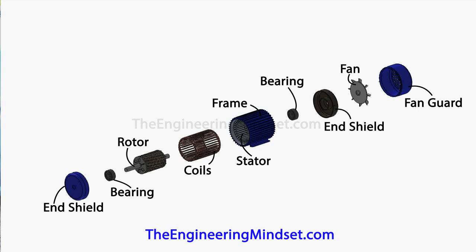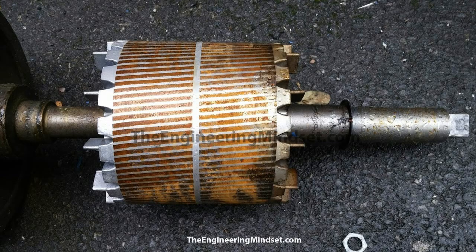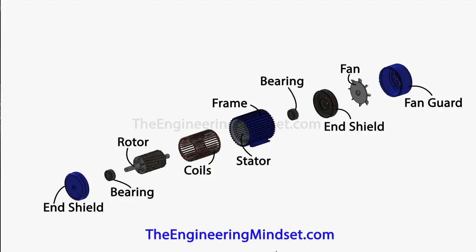The rotor is a shaft with an inductor attached. The inductor is affected by the magnetic field, which causes it to spin. When it spins, it spins the shaft, providing the mechanical power we use to move things. This is a photo of a real rotor — you can see the inductors and the shaft running centrally through the middle. There's also a set of bearings at each end, connected onto the shaft, which fit inside the end shields to ensure the shaft rotates smoothly with minimal friction.